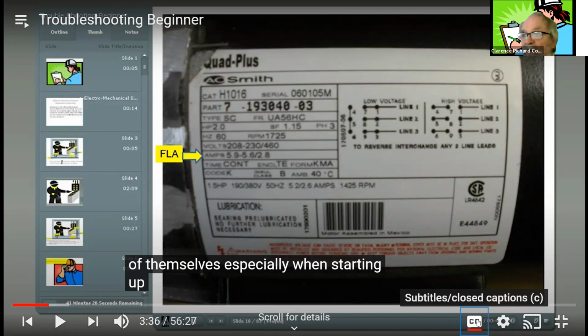Notice that our amps here say 5.9, 5.6, 2.8. The higher voltage you have going to this, the less amperage it's going to use. So this here tells me at its 2 horsepower rating, it's going to take about 2.4 amps. Typically 1 horsepower is about 1.4 amps. And then if you've got 50 horsepower, you take that 1.4 times 50, and that will give you what that amperage is, which might be about 70 amps. So that gives you a feeling for what is on the motor itself.